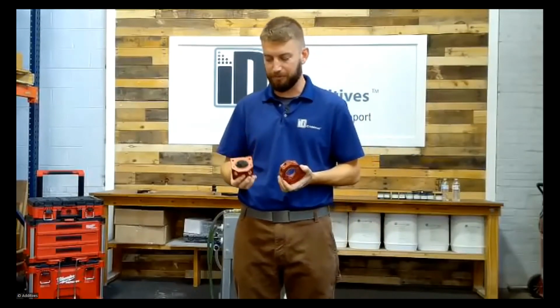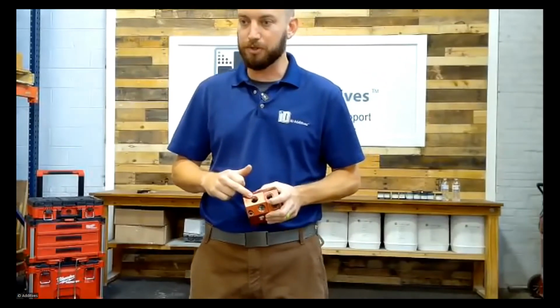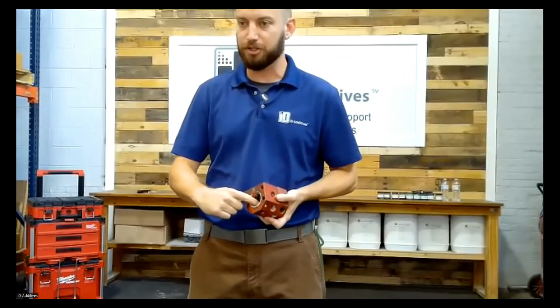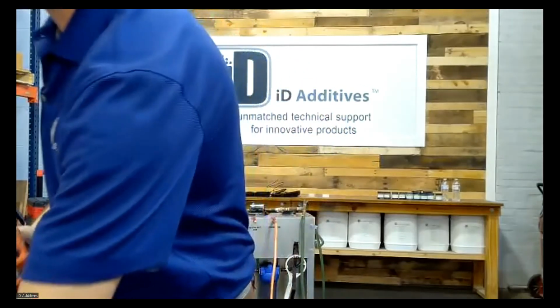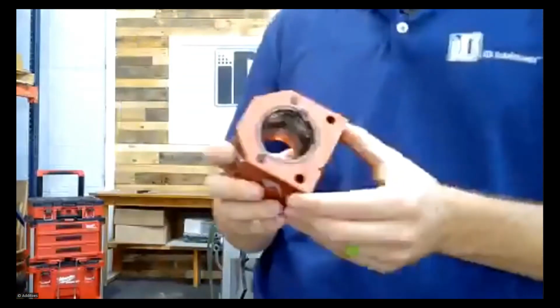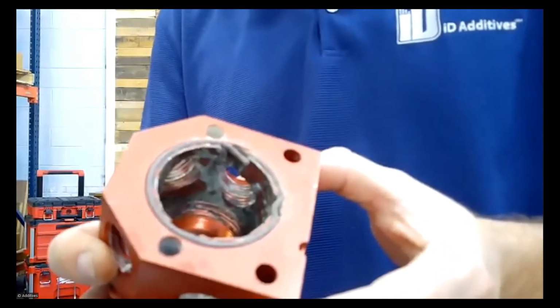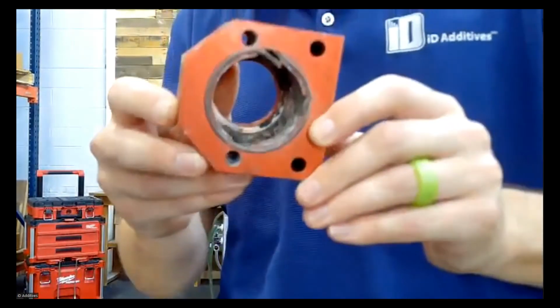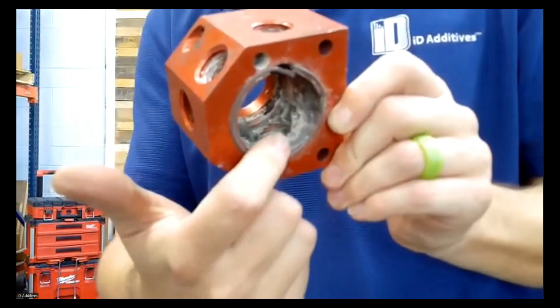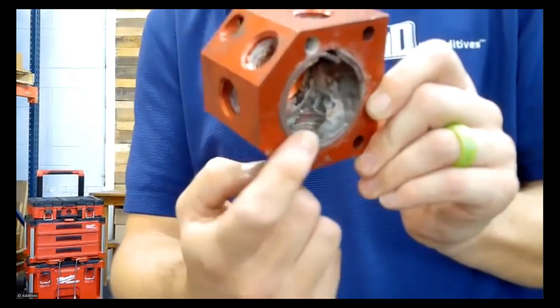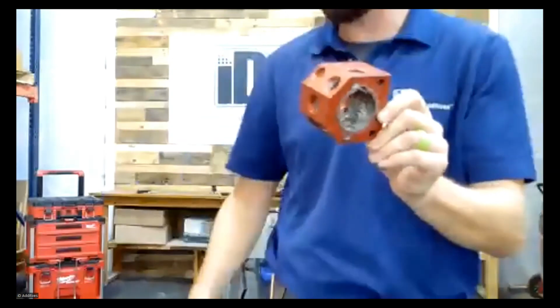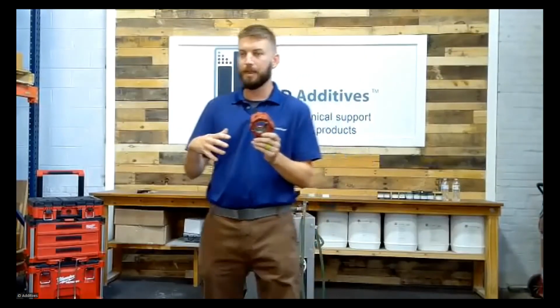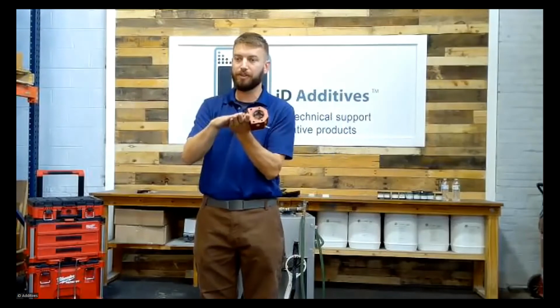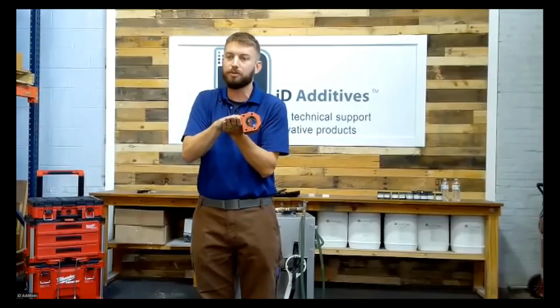But getting back to the manifolds, again, they won't etch any metals, but a common thing to be aware of is, let's say some of these ports weren't plugged all the way and flush with the ID. What can happen is these contaminants start attacking the threads on the inside and eating away your alloys, right? Thereby leaving voids. And what happens is those same contaminants fill that void. Kind of acts like a little Band-Aid. So you don't know there's leaks in there.